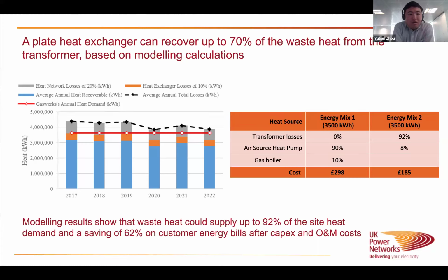In general, a plate heat exchanger can recover about 70% of the waste heat from the transformer based on our calculations, and that will be able to supply up to 92% of the development's heat demand.